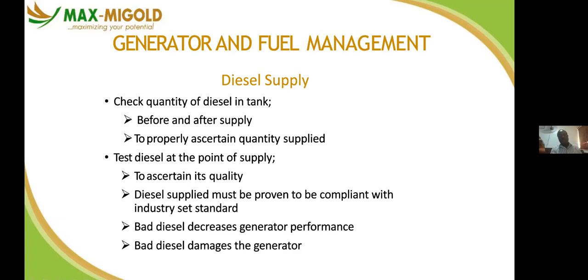Before you take supply, you have to do your diesel test. We have different types of tests to ascertain its quality. Diesel must be proven to be compliant with the industry set standard. Bad diesel decreases generator performance, and bad diesel damages the generator. If you compromise and take bad diesel, it will affect your injector or your fuel line. That will cost you millions of naira to repair.